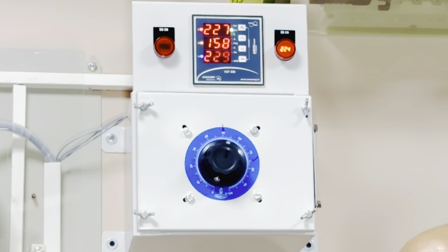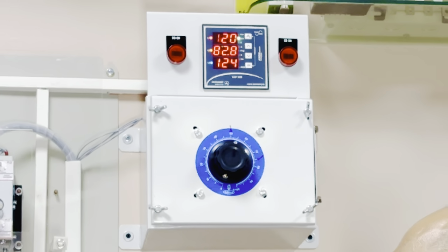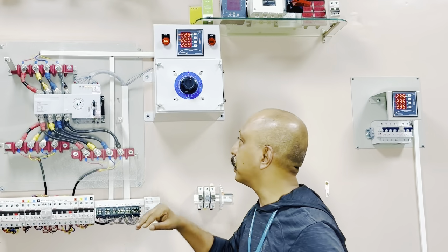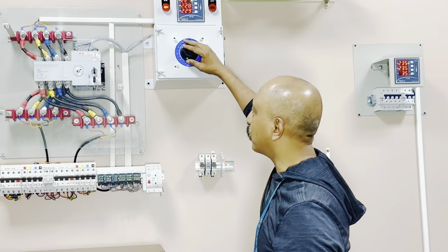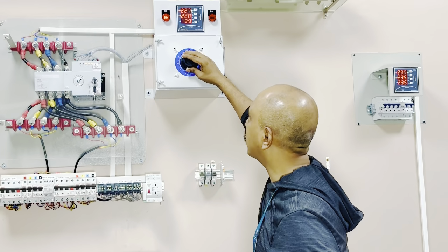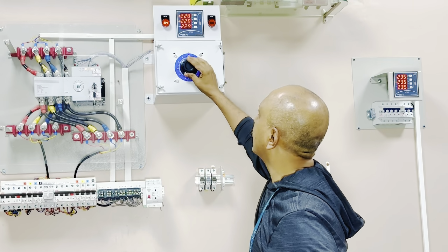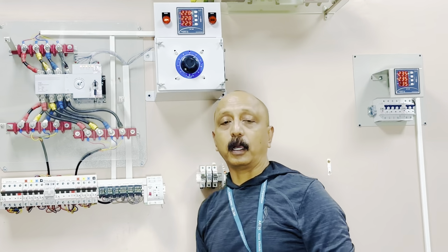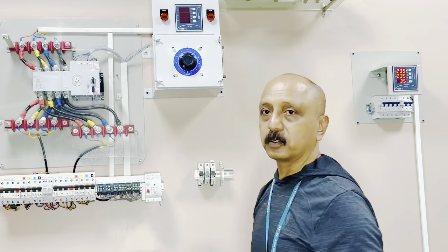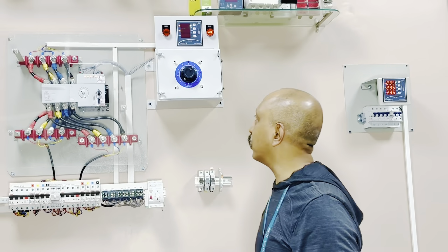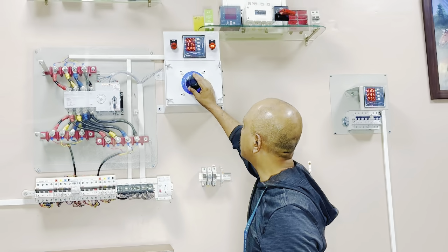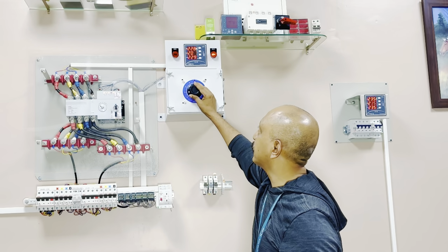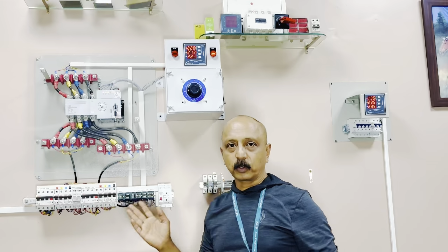When under voltage is simulated, the switch identifies that, goes to zero, and as the generator is available, moves into generator. Now let's assume that the voltage comes back. We have set the threshold level for voltage to recover at about 180 volts. So we are at about 180 volts, and the ATS switches back to normal operations. So that's about under voltage.